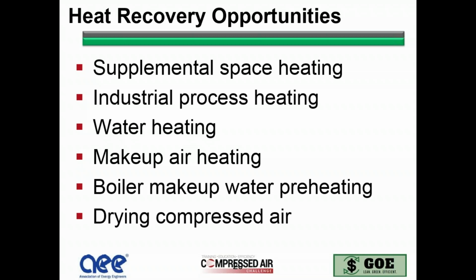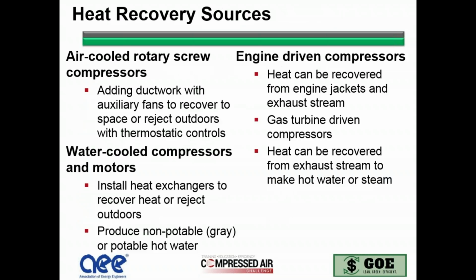And then of course, drying of compressed air, you can also go through and use heat of compression if you have oil-free air compressors, to be able to use heat of compression dryers to actually dry it in a desiccant type dryer. So taking advantage of this is important. Where would you find some of those heat sources? On an air-cooled rotary screw, you can add the ductwork and auxiliary fans to recover as space heat or reject it outside with the thermostatic controls.